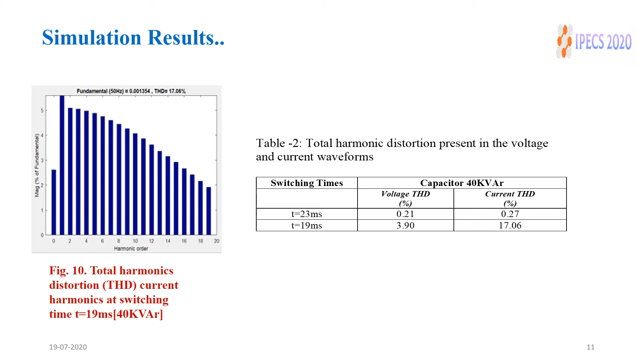So what is the summary? What is the conclusion? Table 2 shows that we select two switching times, 23 and 19, and we measure voltage harmonics and current harmonics. When we switch at 23 millisecond, the harmonics levels, voltage and current, are under 5%. But when we switch at 19 millisecond, my voltage harmonics is okay, under 5% at 3.90%, but my current harmonics is exceeding the standard value. So we have to be very careful when we switch the capacitor very frequently, very fast or very quickly. So that is the conclusion we can get from this result.